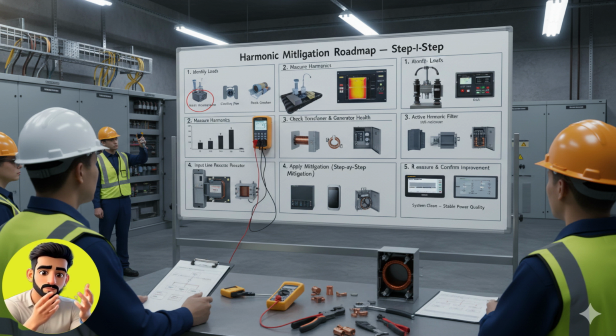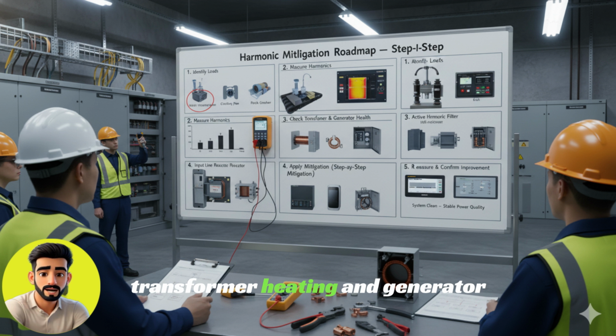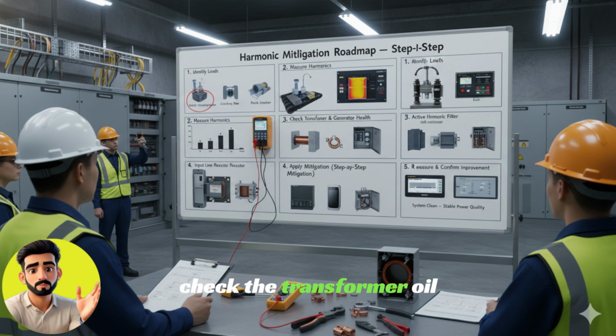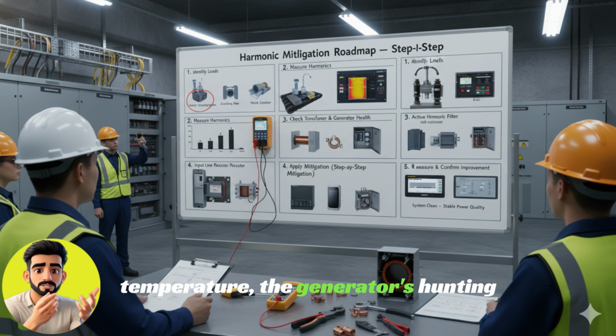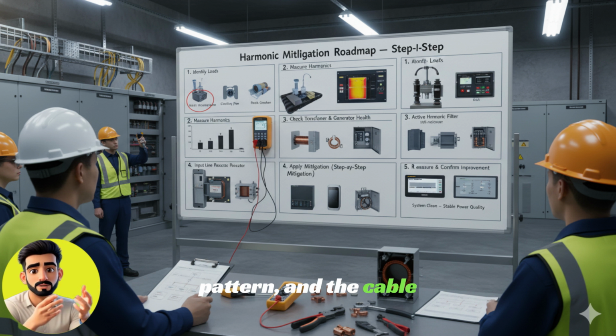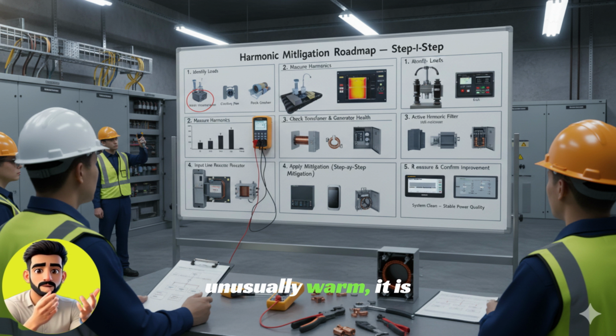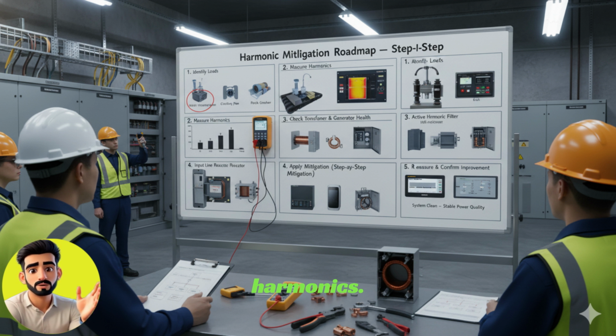The third step is to perform a health check on the transformer and generator. The direct impact of harmonics is seen in transformer heating and generator instability. It is important to check the transformer oil temperature, the generator's hunting pattern, and the cable temperature. If the transformer is unusually warm, it is a strong indicator of harmonics.